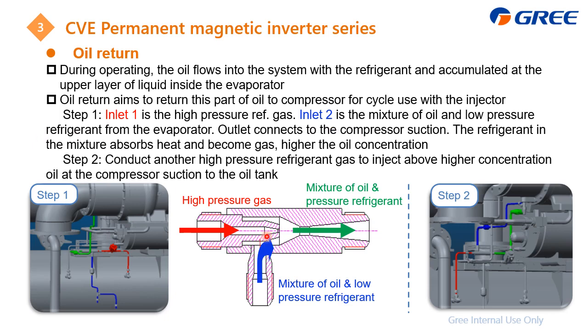When they mix together, it becomes a mixture. On one hand, the refrigerant in the mixture will become gas, which can absorb heat and flow out, and this raises the oil concentration. At step 2, we conduct another high pressure refrigerant gas to inject, which pushes this mixture back toward the compressor for lubrication, and the target is the oil tank. There is an oil pump waiting there, so it can pump the oil into the compressor.